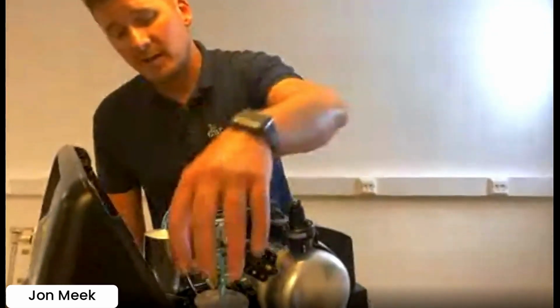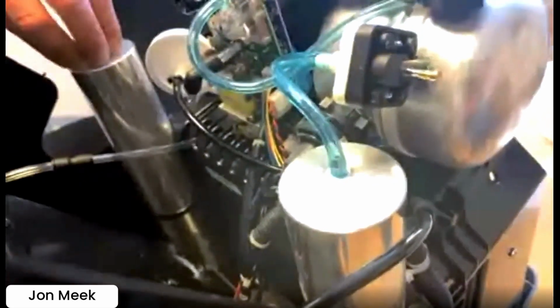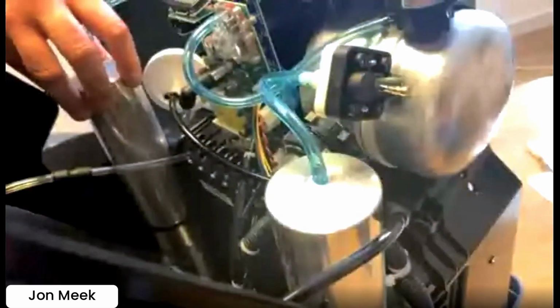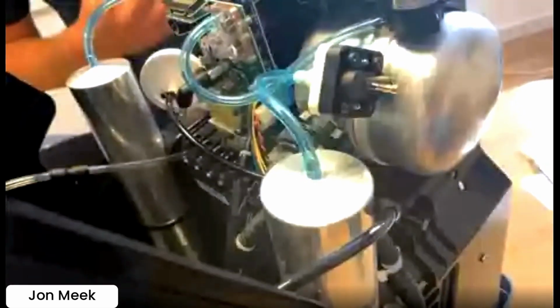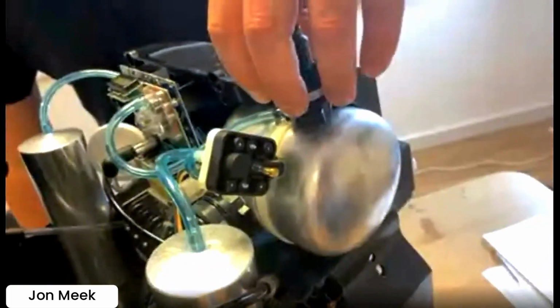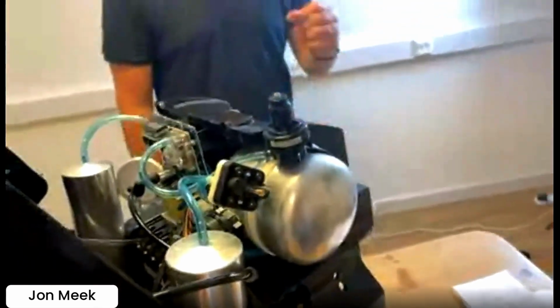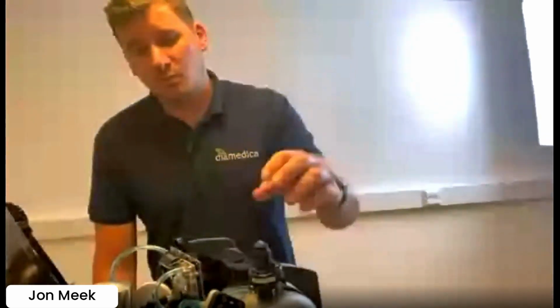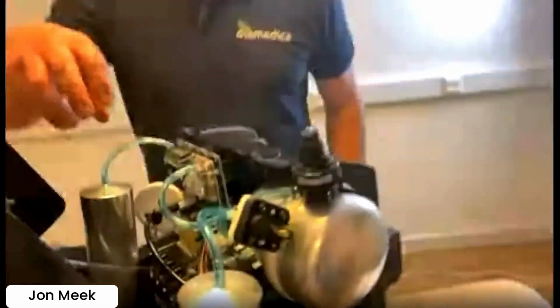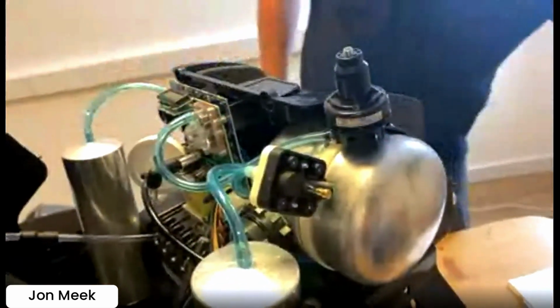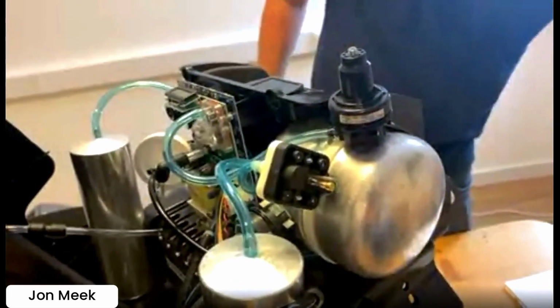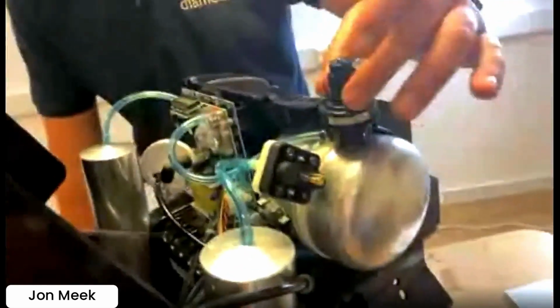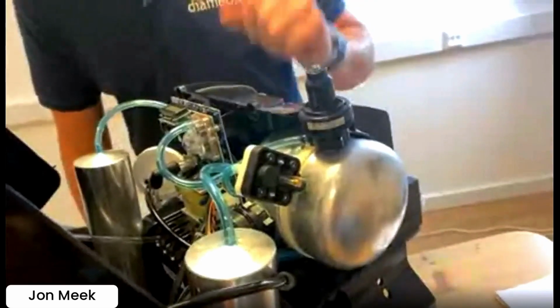So every time they discharge, they regenerate back to new. These are designed to remove moisture as well, but if you use too much flow, these are what's going to be ruined going forward. So if you have too much flow, you will lose a lot of life in your sieve beds, which are really important parts of the machine, and you cannot exceed that flow, otherwise they will be damaged. Coming out of your sieve beds, it goes into an accumulator tank in the side, set with a pressure regulator of 20 psi. So the output pressure is 20 psi. That's the maximum. This is what you want it set to, but also you don't want it coming through your sieve beds any faster than the recommended set flow rates, because you'll deteriorate your sieve beds again. So these should never be adjusted because they're preset and locked in.